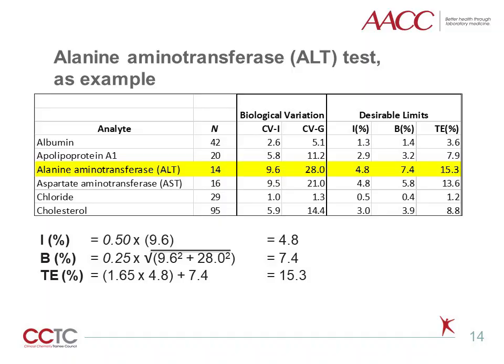Using the alanine aminotransferase (ALT) test as an example: the CVI and CVG estimates for ALT are based on 14 total publications. To get desirable limits for imprecision, we take 50% of CVI, or 9.6, which gives 4.8% for desirable imprecision. For bias, we use the 0.25 factor times the sum of variances of CVI and CVG — that is 9.6 squared plus 28 squared — giving a final result of 7.4%. Total method error equals 1.65 times the imprecision limit of 4.8% plus 7.4% bias, giving a final value of 15.3%.